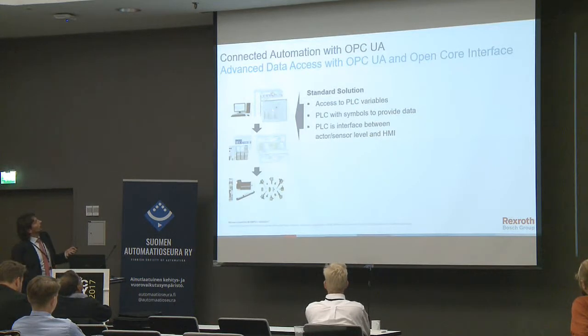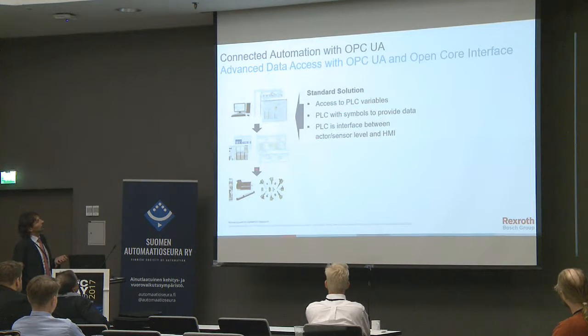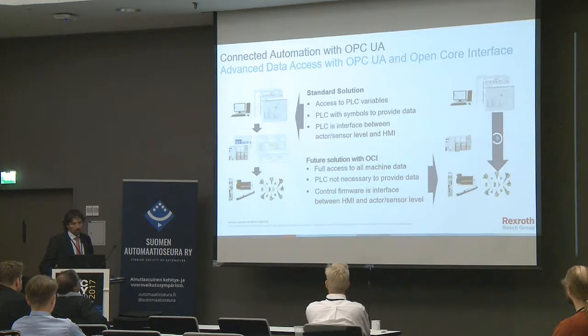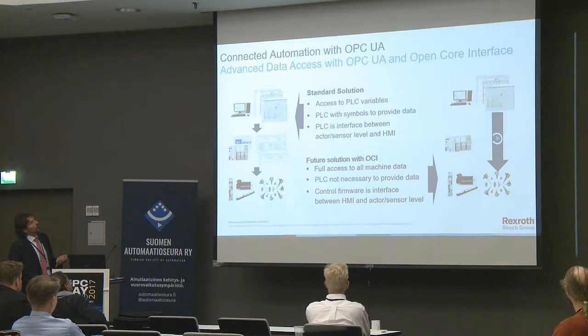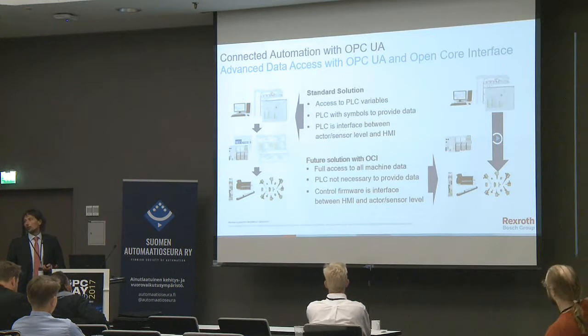Here you can see how communication from an HMI via OPC UA to the sensor/actor level is normally done. The HMI with OPC UA has access to the PLC variables, and the PLC works as an interface between the sensor and actor level. Every variable you want to see has to be programmed in the PLC. In our solution using OPC UA and our OpenCore Interface, we have direct OPC UA access to the actor/sensor level of the machine. The PLC is not necessary to provide the data — all data about the sensor actors is immediately available without changing any line of PLC code.